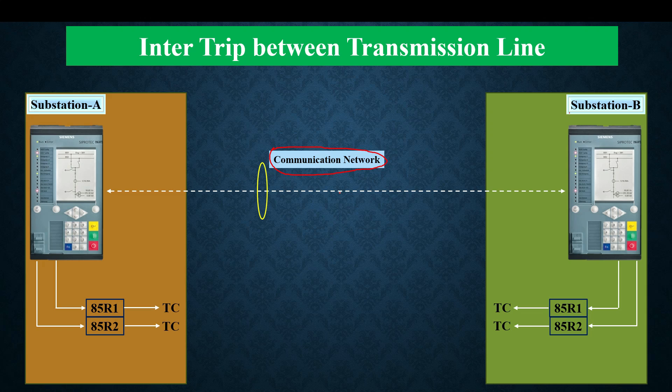Inter trip means that if any protection operates at either substation A or substation B, it should directly go to the other end and operate the lockout relay. At both substations we have two lockout relays named 85R1 and 85R2.